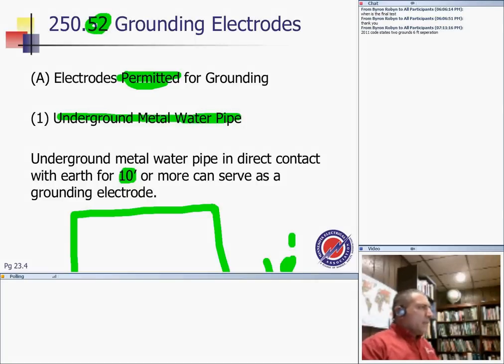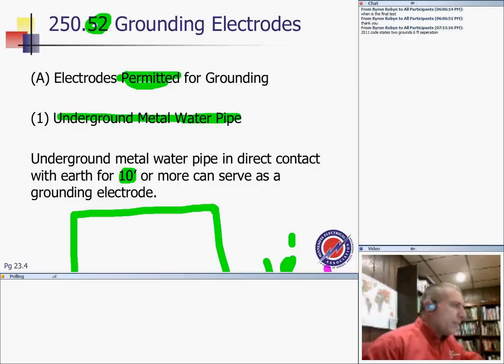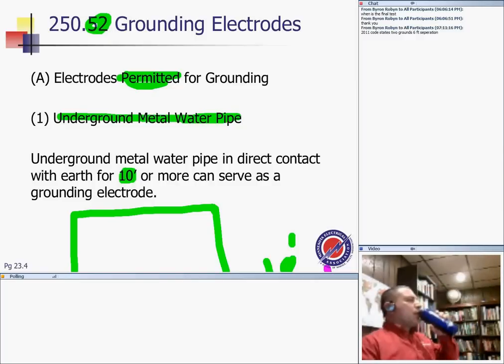So you're building over here, and you need a water pipe in direct contact for at least 10 feet. If it becomes non-metallic here, who cares? You got yourself the 10 feet of contact with pipe. Then you can tie to it as it enters your building. Questions, guys, about the water pipe? Any questions about the water pipe? Water pipe needs supplement though. Remember, water pipe needs to be supplemented.